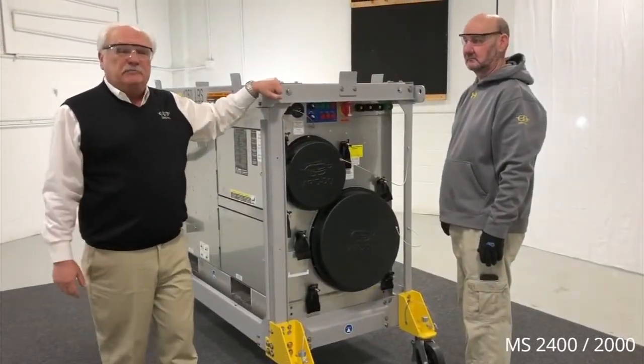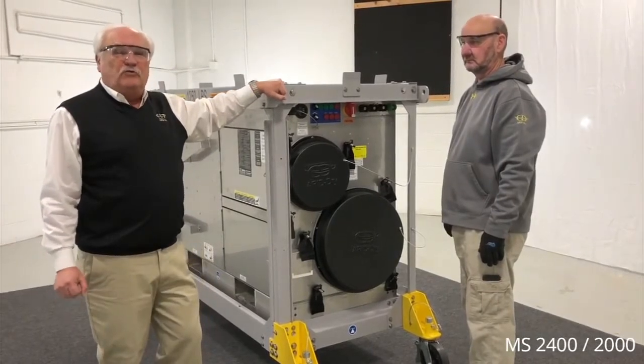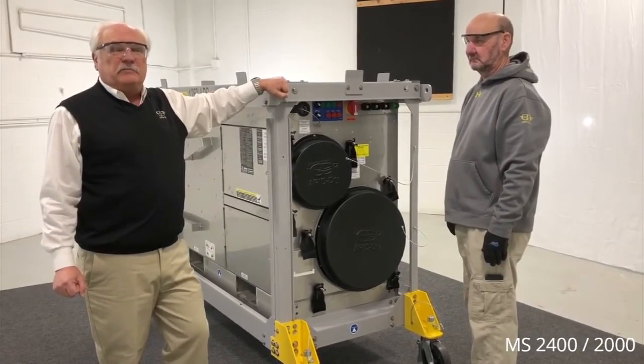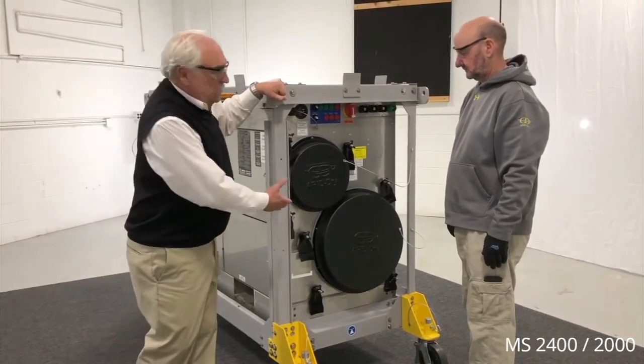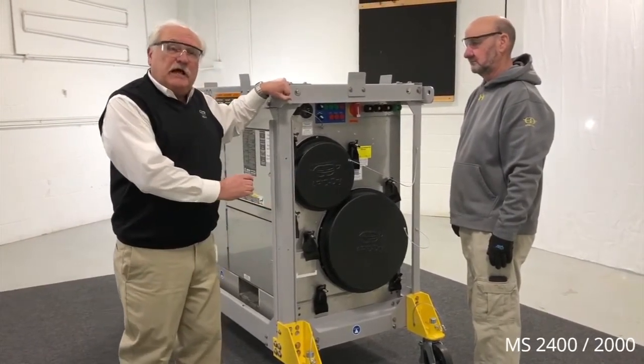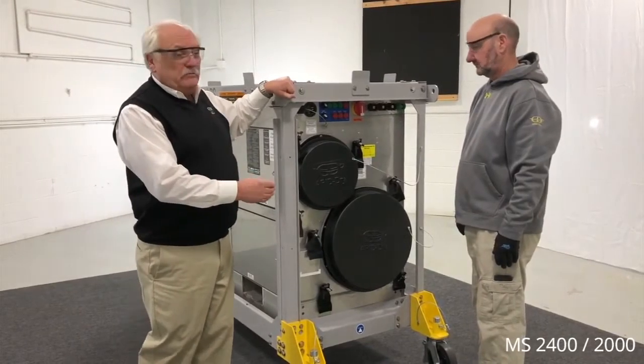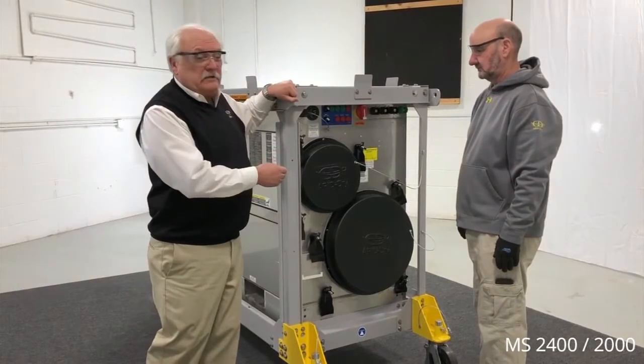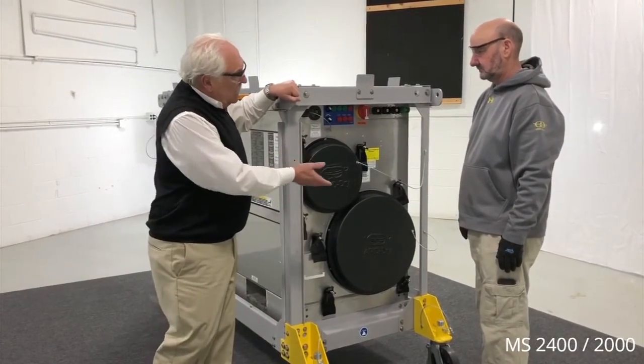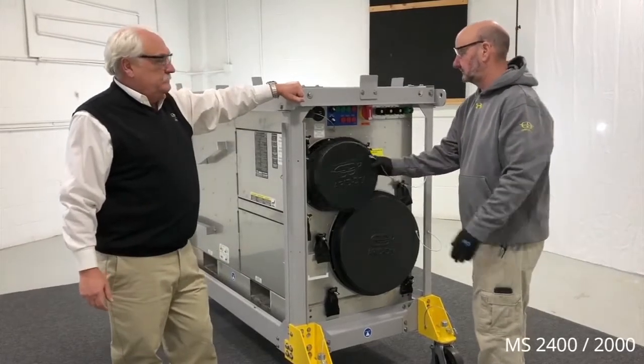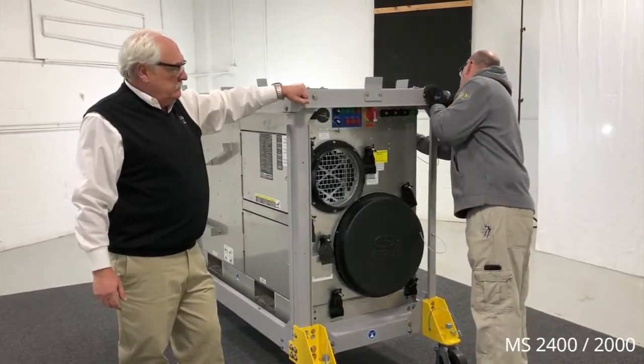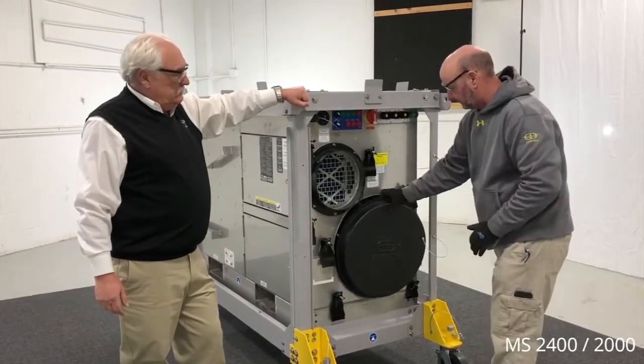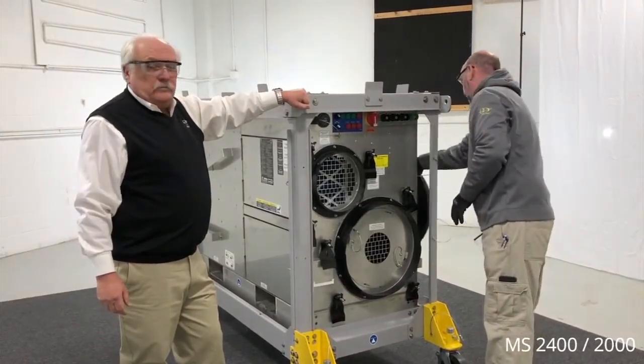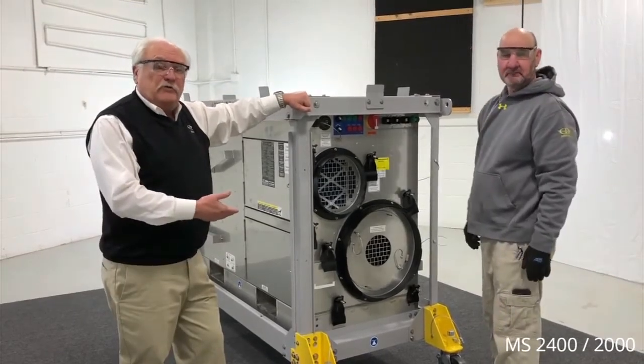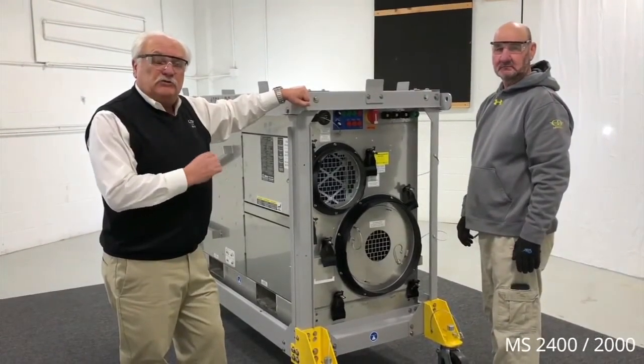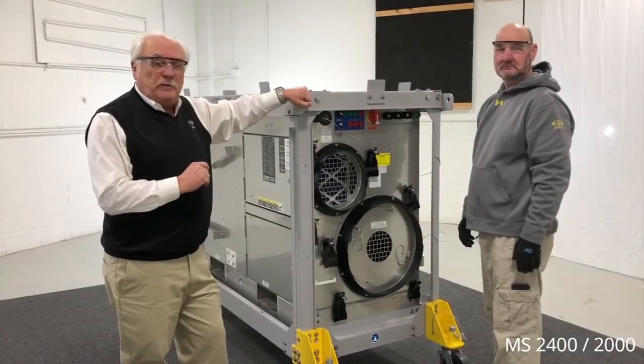The first step to hooking up the MS2400 is removing all 4 shipping covers for the reactivation airstream and process airstream. There are 2 covers located on this end of the unit and 2 covers on the opposite end of the unit. The covers are removed by loosening the quick connect duct clamp, pulling the cover off, and storing it in place on the unit. After these 2 are removed, we move to the opposite end of the unit and remove those 2 covers. All 4 must be removed for proper operation.